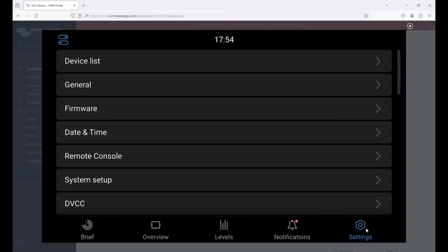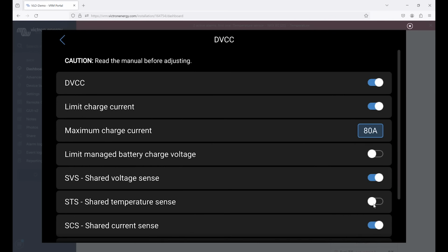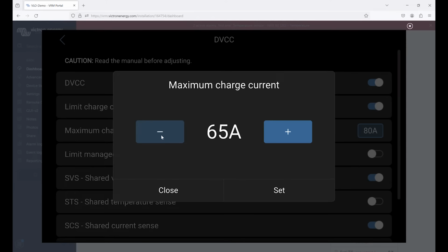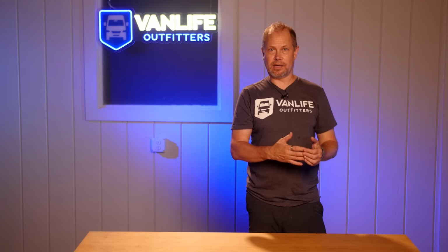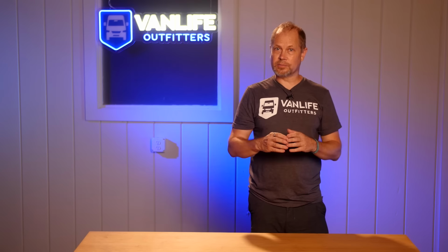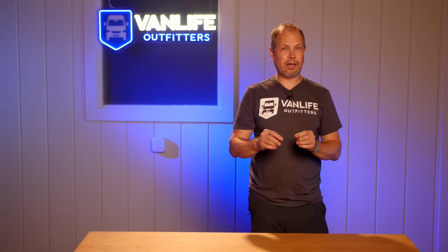One thing you'll notice as we demonstrate the system is that when we set the maximum charging values, the loads on the system are not accounted for unless they are monitored by a dedicated current monitoring shunt. In our tests, there are small DC loads like the Cerbo GX and its touchscreen that are monitored by the SmartShunt in the system, but that SmartShunt is not configured as a DC meter.